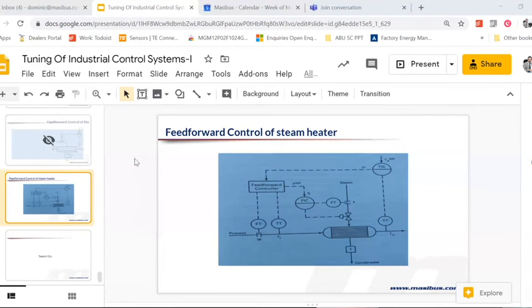Based on all this explanation, you can figure out if there is going to be a long dead time. Dead time is the critical parameter. As I said, take the example of a reactor. By the time you circulate the media in the jacket, there is a transfer of heat to the media in the reactor, then there is a thermowell, then a media in the thermowell, then a sheathing. All this tells you that there is going to be a big lag time. So a cascade will definitely give you better performance and response.